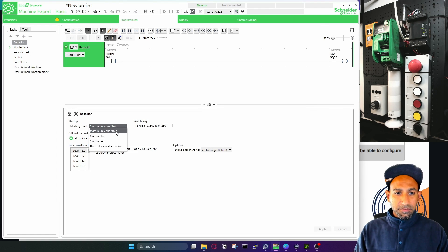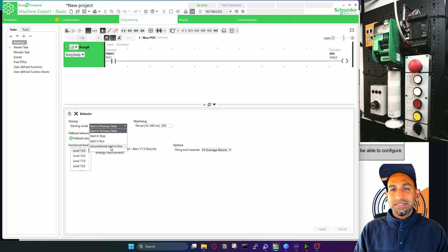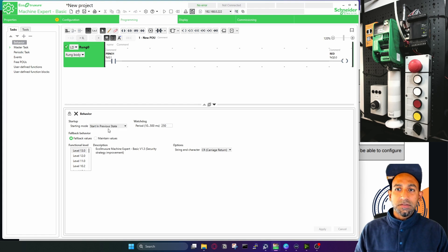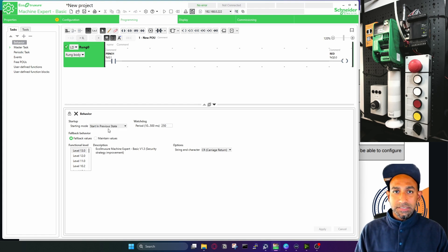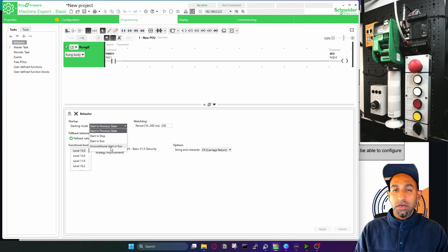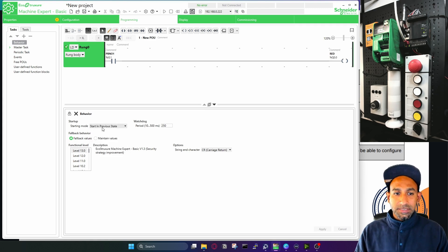It says the startup mode — what should be the startup mode of the PLC or the program? It starts in the previous state, or it should start in stop mode, start in run mode, or unconditional start in run mode. By default it's in previous state, so it will start in whatever the previous state was. You can change it to stop or run mode, but unconditional start in run mode is dangerous. I'll keep it in previous state.